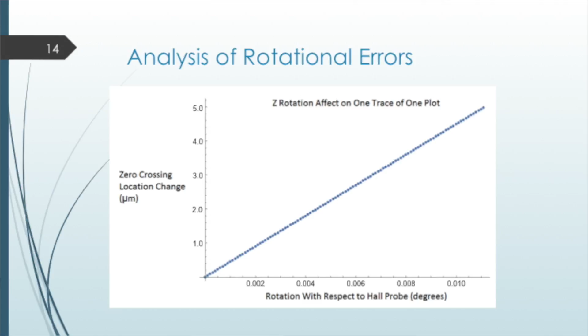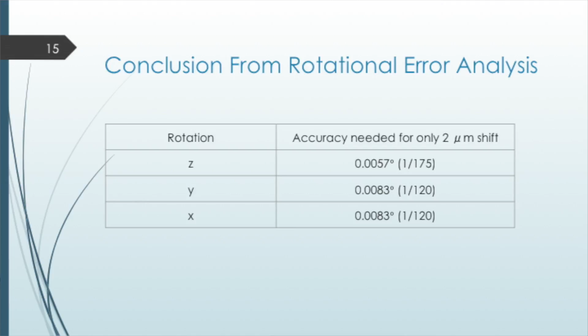What this shows is the effect of Z rotation on one of the traces of one of the plots. So one of these lines on one of these plots, so this is just one plot, I guess. On the x-axis, we have the rotation with respect to the Hall probe in degrees, and on the y-axis, we have the location shift. So that just shows the effect. From many plots like that, we came to the conclusion that in order to achieve an accuracy of only 2 micrometer shift in those field peak locations, we would need in the Z direction about 1/175th of a degree, and in the X and Y about 1/120th of a degree. So when we design our mechanical system now, that's the accuracy we're aiming for.